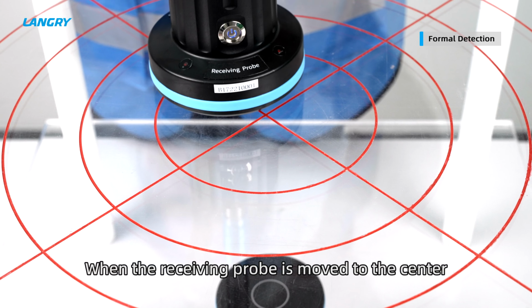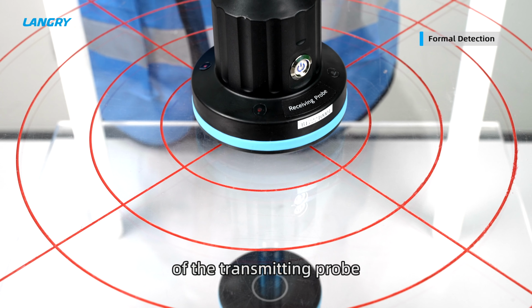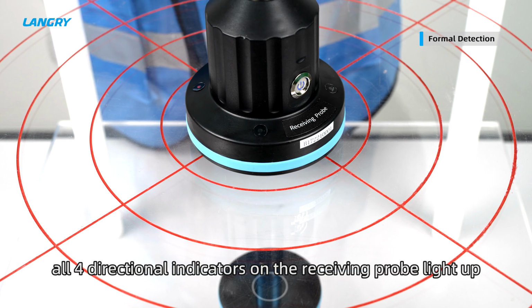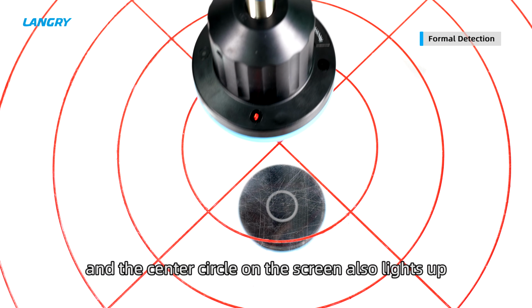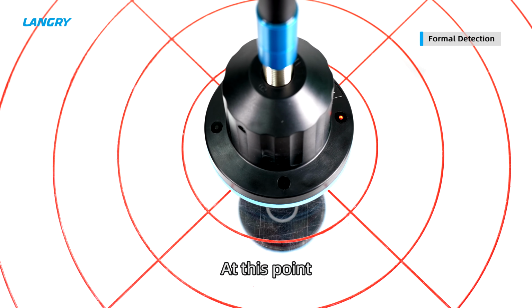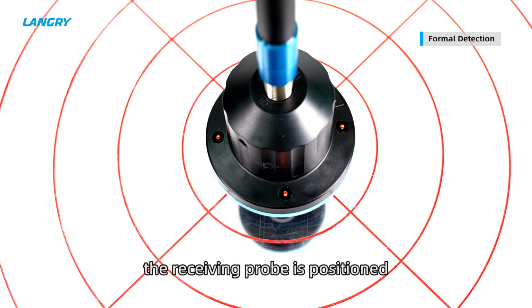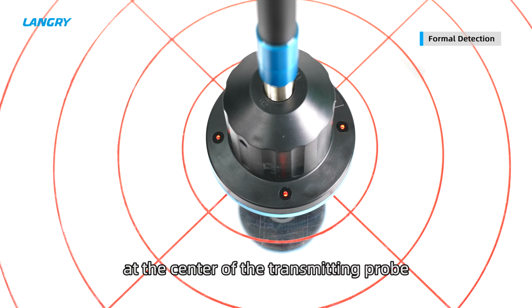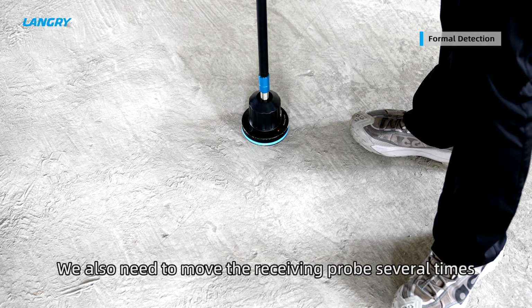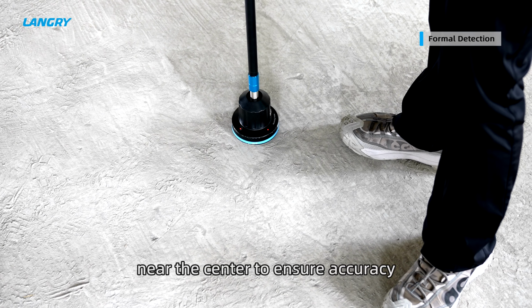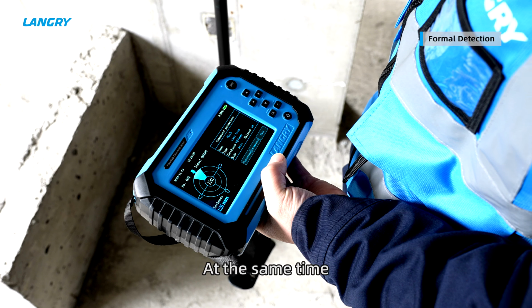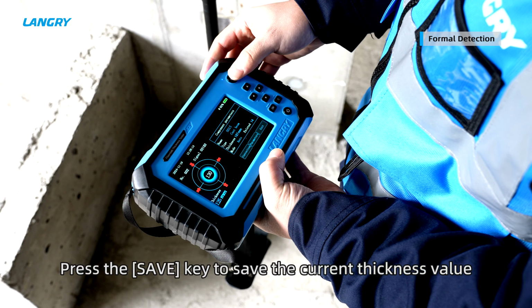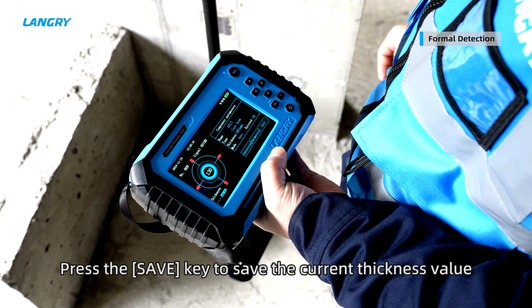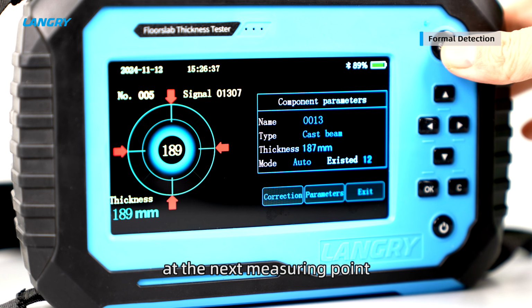When the receiving probe is moved to the center of the transmitting probe, all 4 directional indicators on the receiving probe light up, and the center circle on the screen also lights up. At this point, the receiving probe is positioned at the center of the transmitting probe. We also need to move the receiving probe several times near the center to ensure accuracy. At the same time, the instrument automatically locks the minimum effective thickness, which is the true thickness of the floor. Press the Save key to save the current thickness value, and proceed to the measurement at the next measuring point.